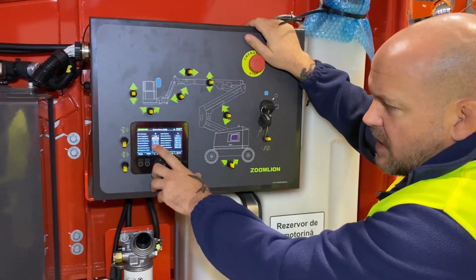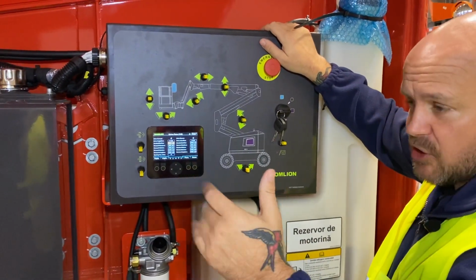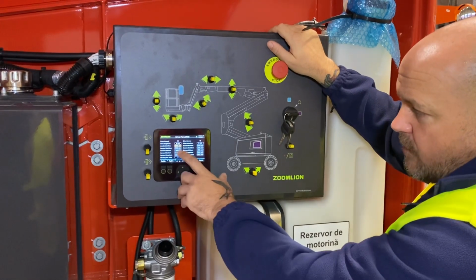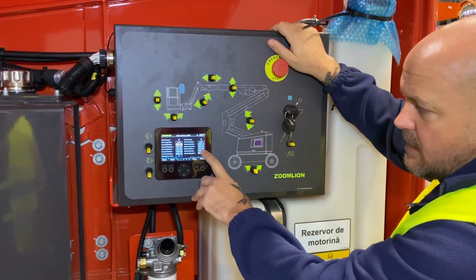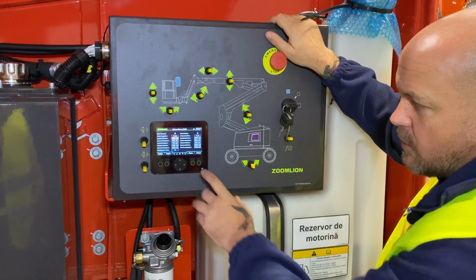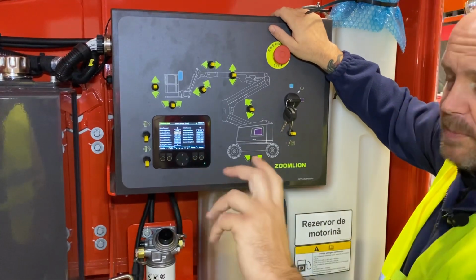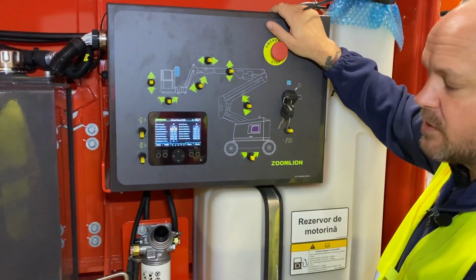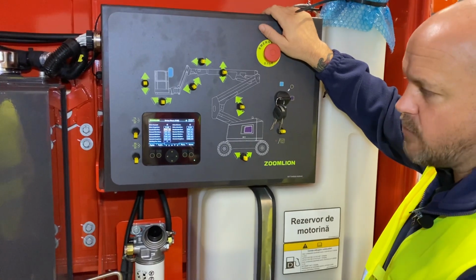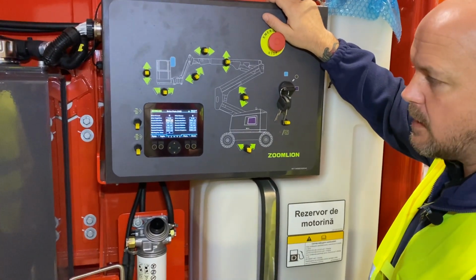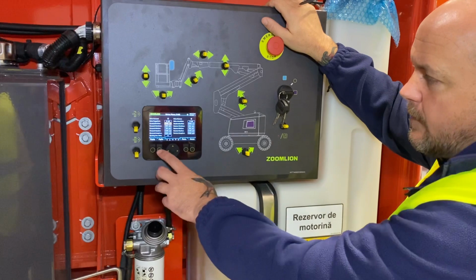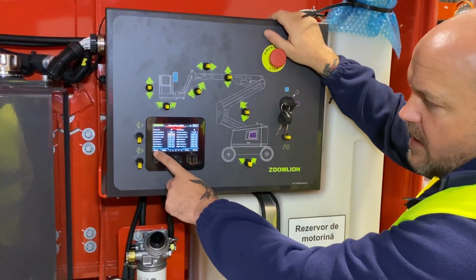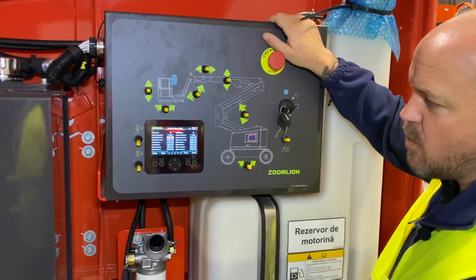We can also set the minimum current times, which is when the machine is switched to slow speed drive. The maximum current we get then is 790 and 790. And we can also set the creep current drive, because when you switch the boom speed control into creep, that can also affect the drive system as well as the boom system. Okay, so if we can scroll down using the page up and page down buttons, now we're into swing parameters.